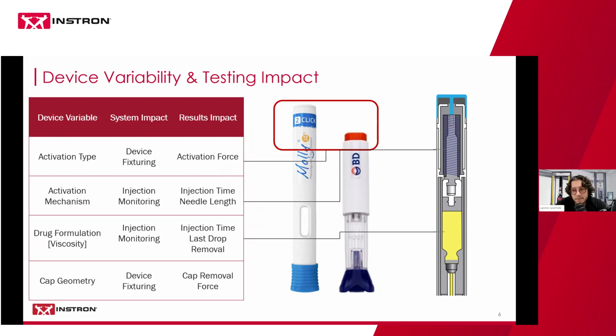In a similar vein, the drug formulation itself has a major impact on testing these devices. Throughout the development process, we would always say, if we had to design the system to work for one device type with one fluid viscosity with one needle length, this would have been a very easy project. It's trying to make it work for the entire range of device form factors and needle gauges and fluid viscosities that makes it challenging and makes it interesting. So the drug viscosity will have a major impact on, like I mentioned earlier, the injection time, but also trying to remove the last drop from the tip of the needle at the end of the test is very difficult depending on the viscosity of the fluid. It tends to be harder to move the higher viscosity fluids, and we needed to make sure we designed the last drop mechanism to support a full range.